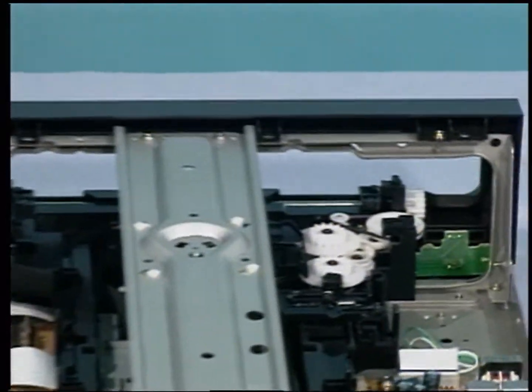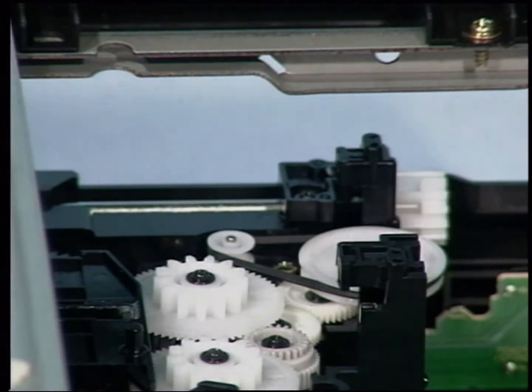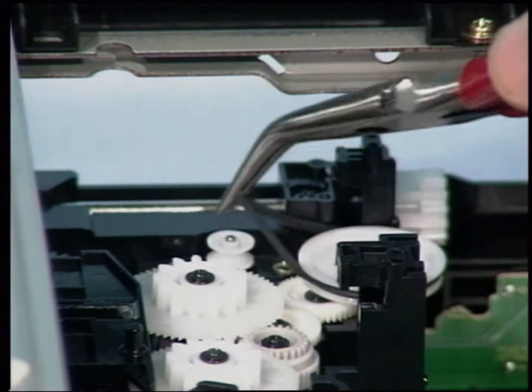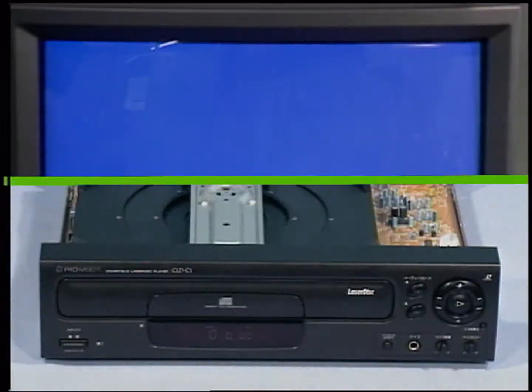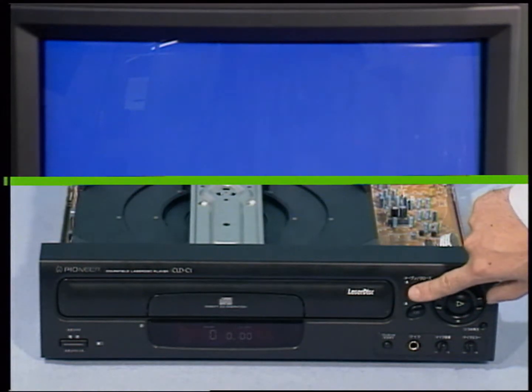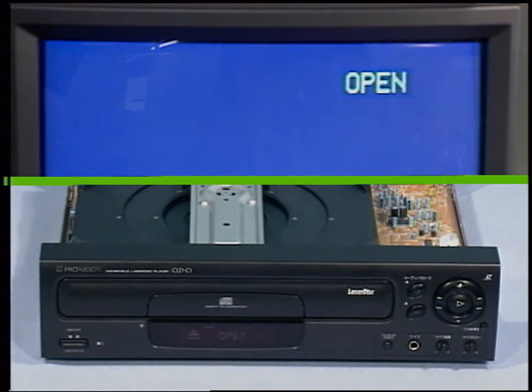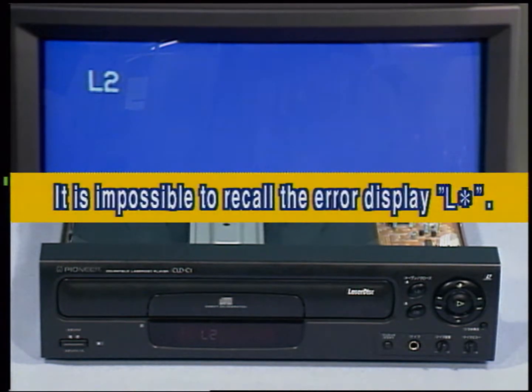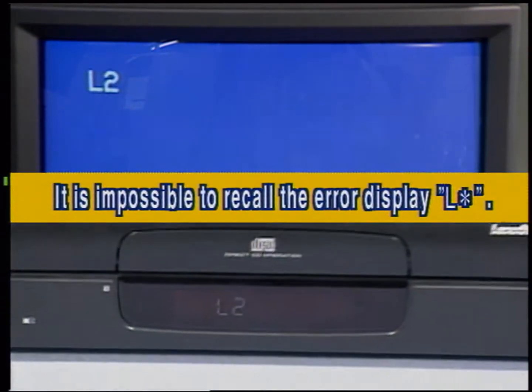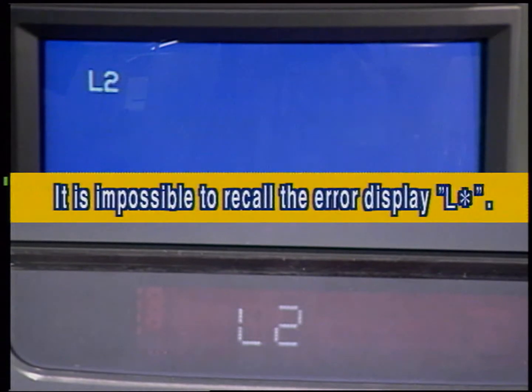To make a failure in the loading operation, the loading belt is removed from the motor pulley. In this condition, once you open, the tray won't open, and the loading operation comes to the time over. As a result, the error code L2 is displayed. The error code starting with L is called the loading error. Regarding the loading error, you cannot recall the error code after it is erased.